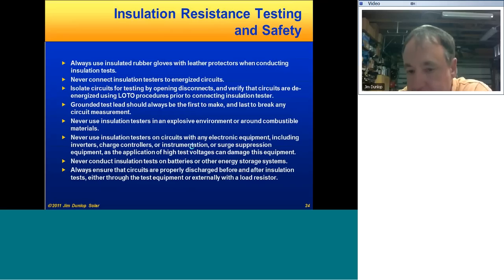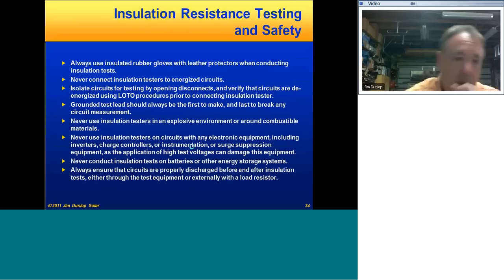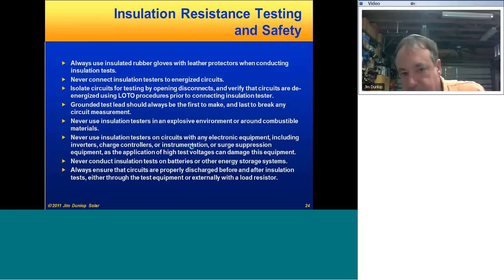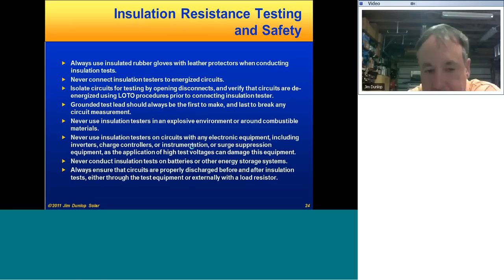Never use the insulation testing in explosive environments, or don't ever test any circuits that have sensitive electronics in it or surge protection equipment or anything like that, or batteries. Make sure all circuits are discharged, any capacitors or anything in there, or wiring system, the normal capacitance needs to be discharged, so wait a few minutes after you de-energize circuits before you conduct these tests.